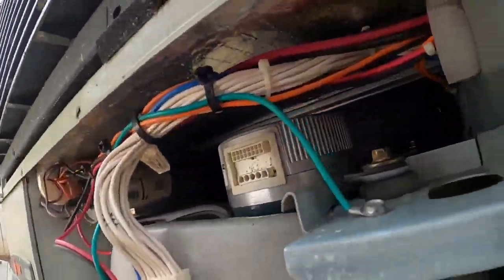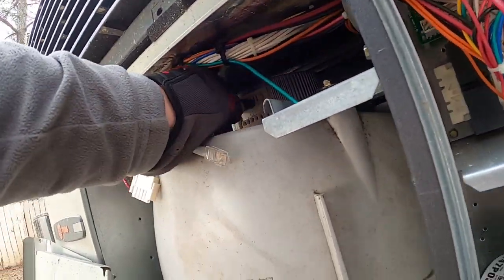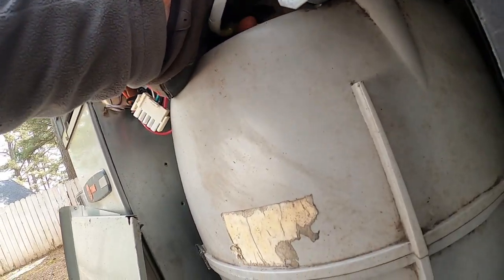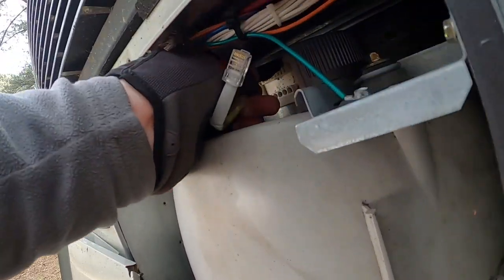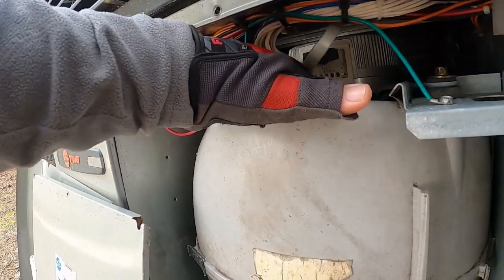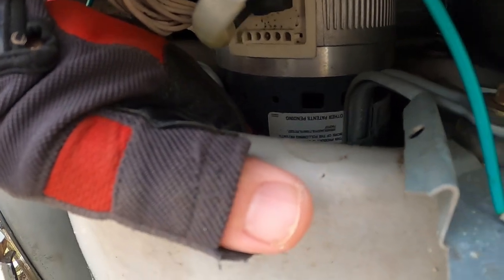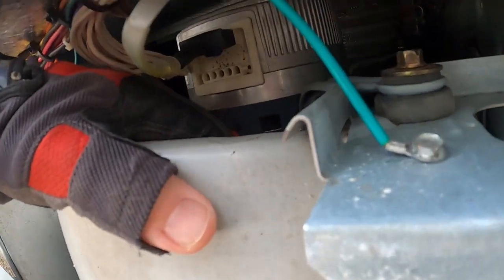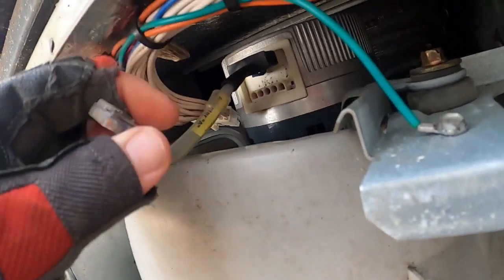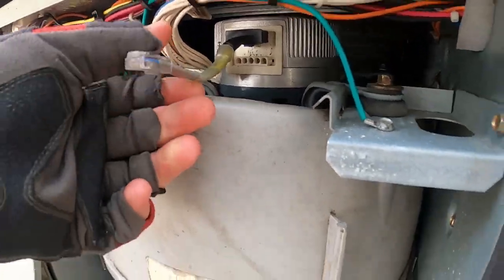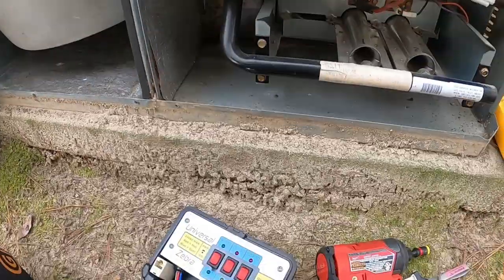And this is a 16 pin variable speed motor. So as long as that motor spins free, which it does, more than likely if there's a problem with this, it's just going to need a new module, not the whole motor. So let's see what happens when I get this thing hooked up.